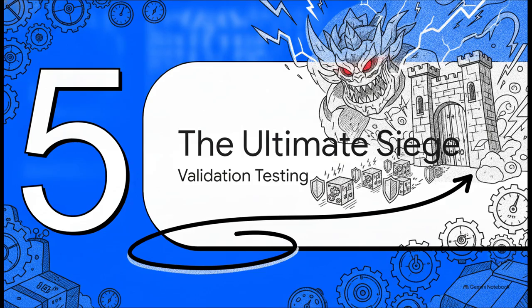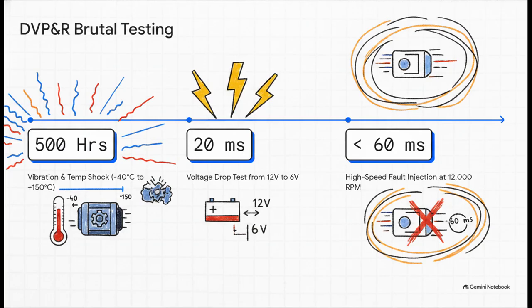And finally, Section 5, the ultimate siege. Validation testing. Before any of these inverter units are allowed anywhere near mass production, they have to survive a brutal final boss sequence of validation tests. And I mean punishing. The engineers subject these units to a vicious combination of thermal shock, literally slamming the temperatures from negative 40 to positive 150 degrees Celsius, while simultaneously hitting it with 3-axis random vibrations for 500 hours straight. While it's being shaken and baked, they forcefully drop the power down to 6 volts for 20 milliseconds just to prove those backup capacitors do their job.